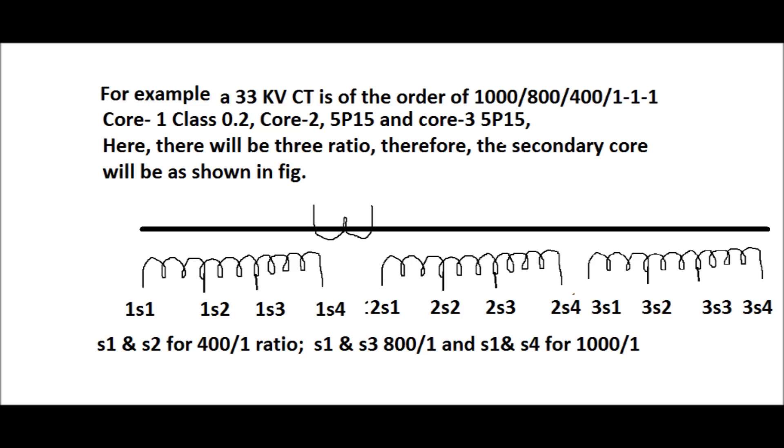In this case, the common is S1 terminal and the other terminal is used with the help of S1. That is S1 and S2 or S1 and S3 and S1 and S4. If first and second core are used and the third core is not used, then third core shall be always shorted. If not shorted, then there will be chances of CT damage that will be discussed later.